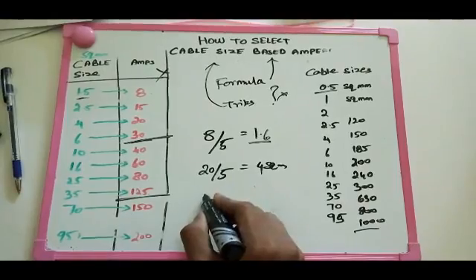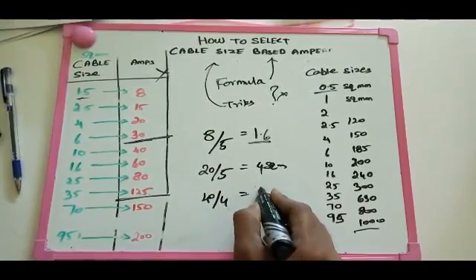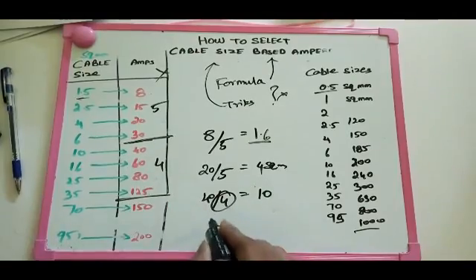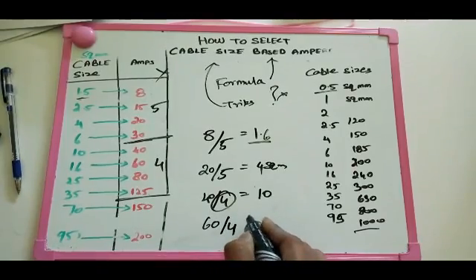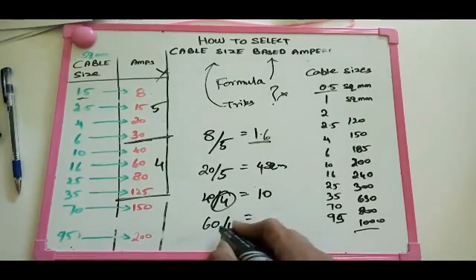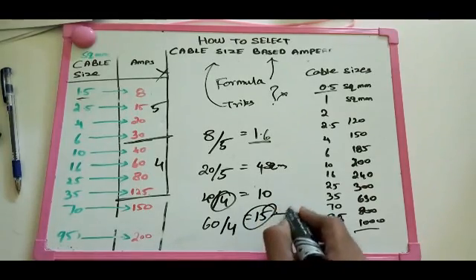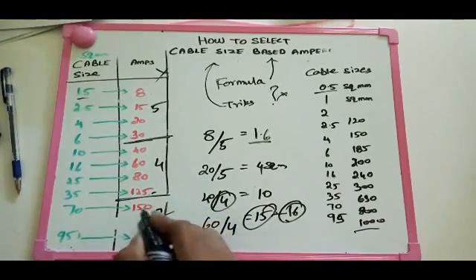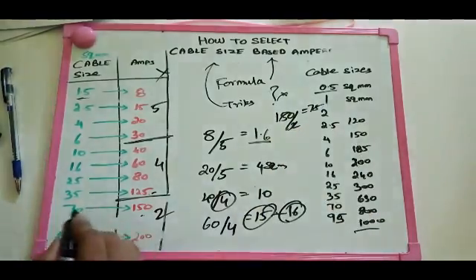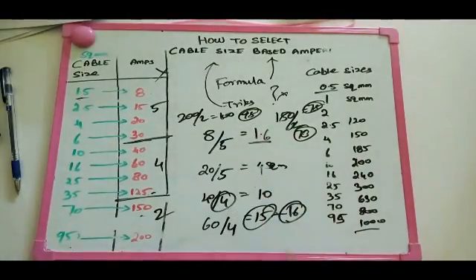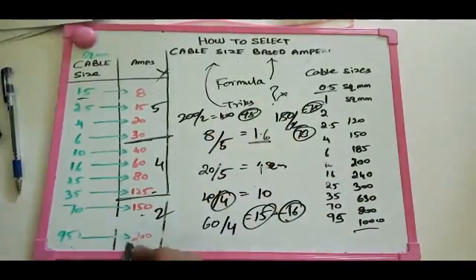From 32 to 125 ampere, you need to divide by 4. For example, if you have 60 ampere, divide by 4 and you get 15, so you select 16 square mm cable. For 125 ampere, divide by 4 and you get about 31, so select 35 square mm. Above 125 ampere, divide by 2. For 150 ampere, divide by 2 and you get 75 — more or less, we take 70 square mm. For 200 ampere, divide by 2 and we get 100 — more or less, we take 95 square mm. This is an approximate trick, not an exact formula.